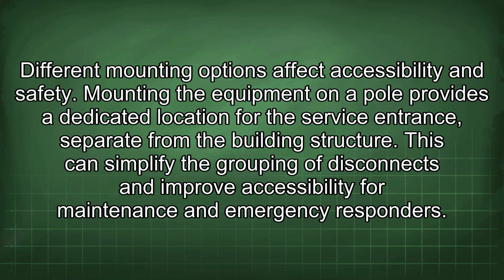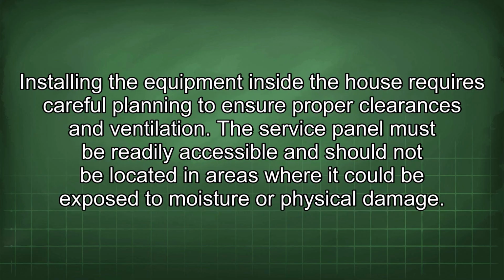Mounting the equipment on a pole provides a dedicated location for the service entrance separate from the building structure. This can simplify the grouping of disconnects and improve accessibility for maintenance and emergency responders. Installing the equipment inside the house requires careful planning to ensure proper clearances and ventilation. The service panel must be readily accessible and should not be located in areas where it could be exposed to moisture or physical damage.